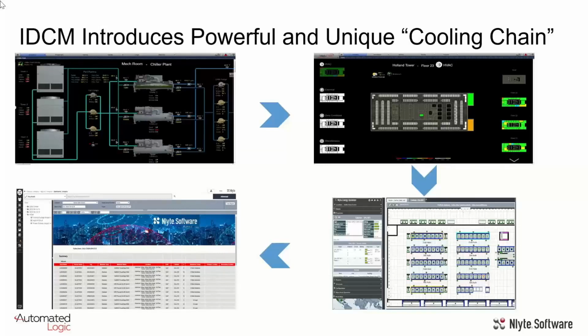In the way this has been architected, this cooling chain is exceptionally flexible. You can define what the endpoint of the cooling chain is - whether it's the evaporative system, the cooling tower, the chiller, or the air handler. You can define what that endpoint is, and then dynamically define all of the assets that are affected by those cooling components.